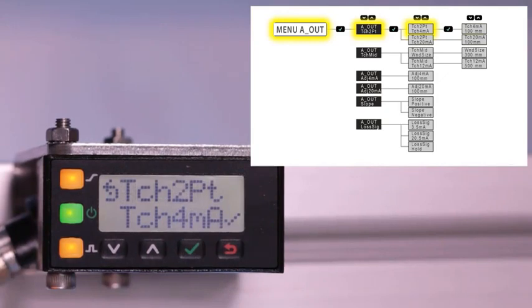When using two-point teach, the 4 and 20 milliamp limits are taught separately. So it is possible to teach both limits or just re-teach a single limit while leaving the other unchanged. The first option seen within the teach two-point menu is Teach 4 milliamp.